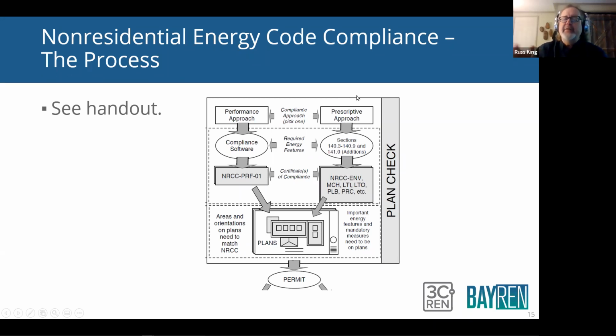They're relatively simple projects, just an alteration, you know, just a lighting change, just an HVAC change out. It's not really worth it to do a whole computer model and all that jazz. So just use the prescriptive approach. So for the prescriptive approach, we've got certain sections of the code that apply. Here are those sections there. And you have certain forms, all right? I mentioned the NRCCs. Well, they're broken into the different components. So you've got your NRCC envelope, mechanical, lighting, and you'll use the forms that apply to your project. If you're not touching the plumbing system, you don't need to fill out any plumbing forms. If you're not touching the lighting system, you don't need to fill out any of the lighting forms. So what you're touching, and when I say touching, I mean altering, what you're altering will determine which forms you need to fill out, all right?